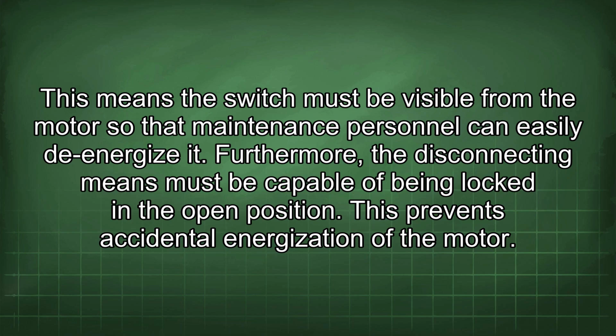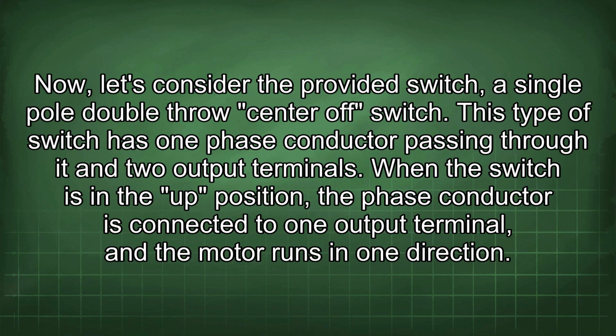Furthermore, the disconnecting means must be capable of being locked in the open position. This prevents accidental energization of the motor. Now let's consider the provided switch, a single-pole double-throw center-off switch. This type of switch has one phase conductor passing through it and two output terminals.